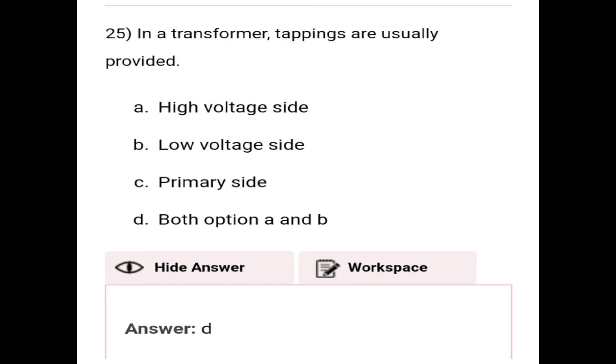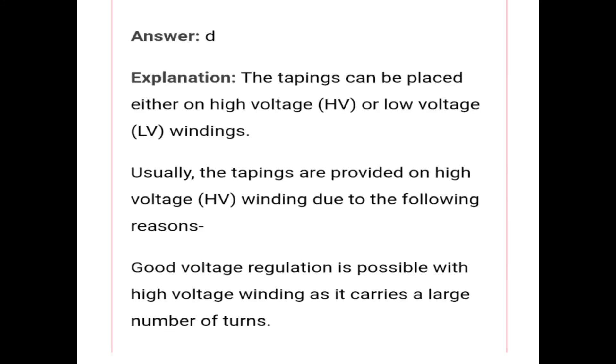Next question: In a transformer, tappings are usually provided on high voltage side, low voltage side, primary side, or both A and B. The correct answer is option D, that is A and B, meaning high voltage side and low voltage side. The explanation is that the tappings can be placed either on high voltage or low voltage winding. Usually the tappings are provided on high voltage winding due to the following reasons: good voltage regulation is possible with high voltage winding as it carries a large number of turns.